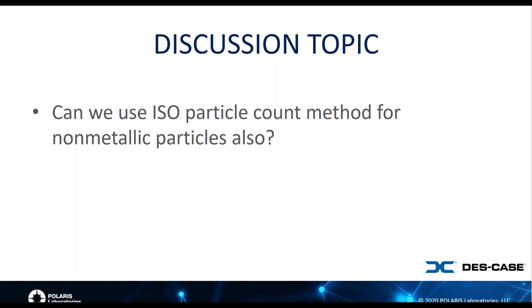To try to determine how much of that's metallic, you would have to combine our particle count with something like PQ, which is a particle quantifier, which is measuring that ferrous material, as well as looking at the standard elemental analysis we've got. You guys agree with that one? I do. Go ahead. Yeah, I was going to say I do, Bob.